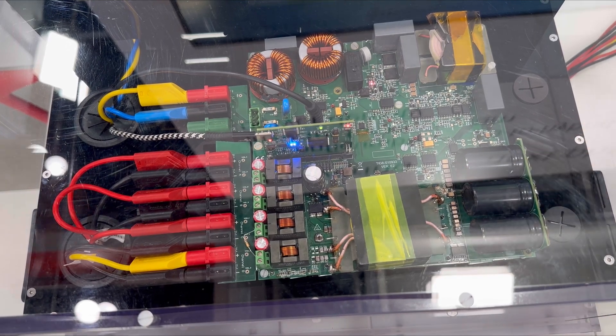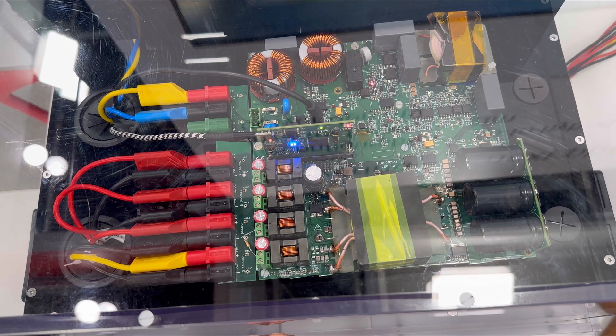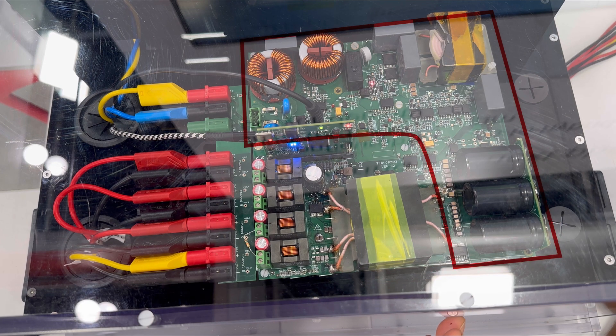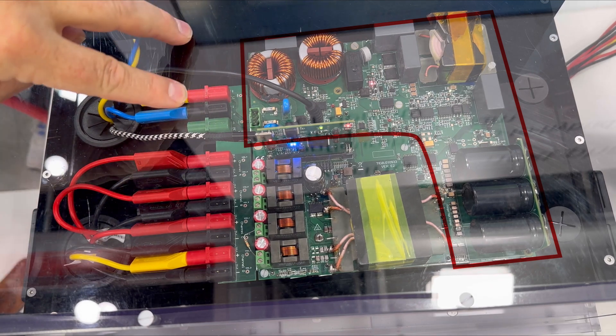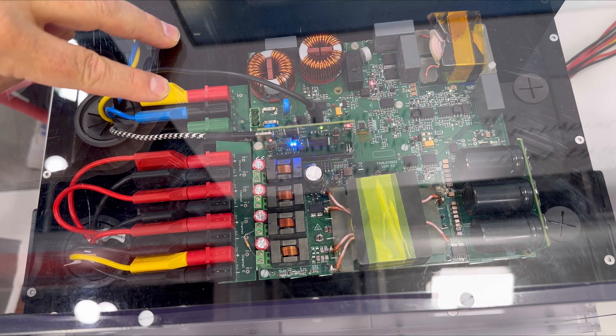The four boost stages can also operate in reverse to charge and discharge a battery. The GaN devices are on the back side of the PCB because we have a bottom-side cooling system — the back side is connected to a heatsink allowing convection cooling with no additional cooling needed. The second stage is the CLLC stage with a big transformer in the middle, converting from the 75-volt rail to the 400-volt rail. From the 400-volt DC link we generate AC voltage via a totem-pole PFC connecting to the grid. The AC output — shown in yellow and blue — can be 230 volt or 110 volt for different grid systems.